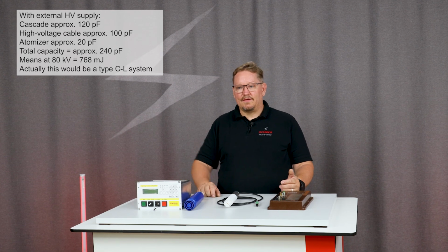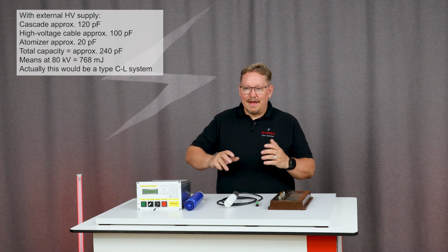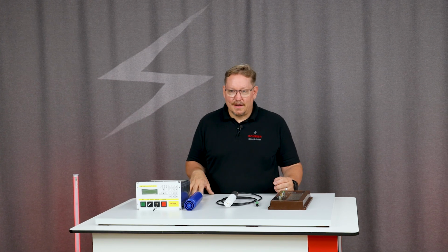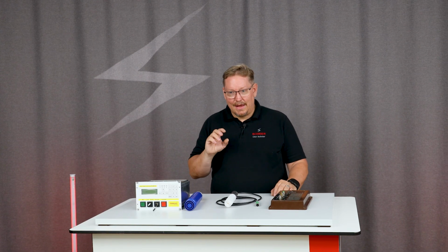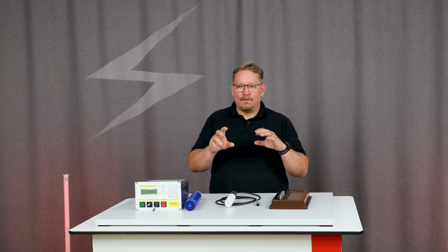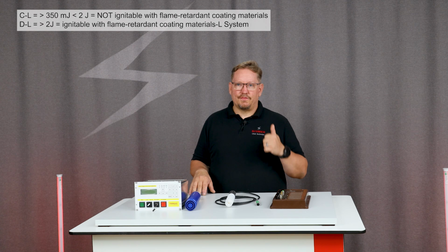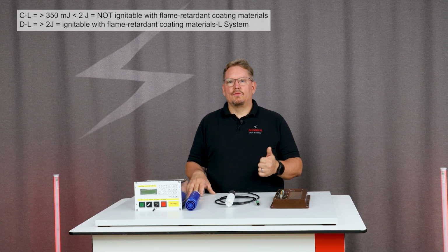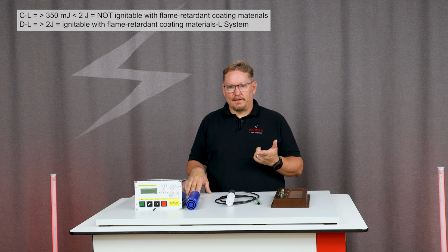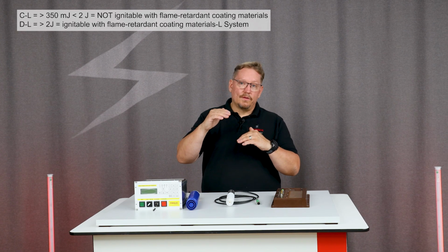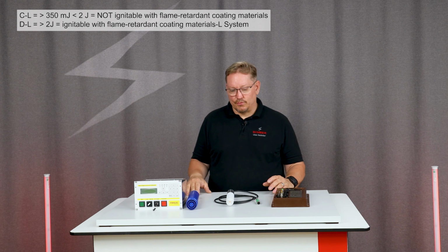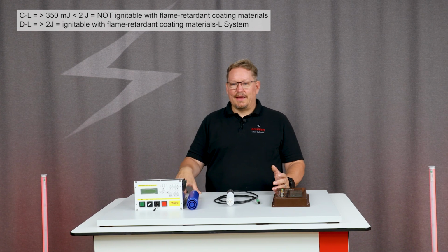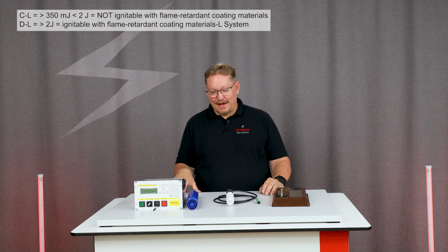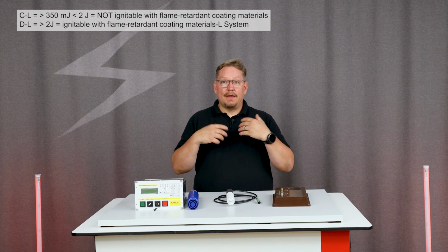In the range above 350 mJ, we will automatically be using either a CL system or a DL system. In future, the two classes will probably be combined into L3 types. So, the distinction between CL and DL types in the standard was actually only about flame retardant coating agents and normal flammable coating agents. This means that whether I am above 2 joules or below 2 joules will no longer play a major role in future. This means that we are actually always in the flammable range for all systems.